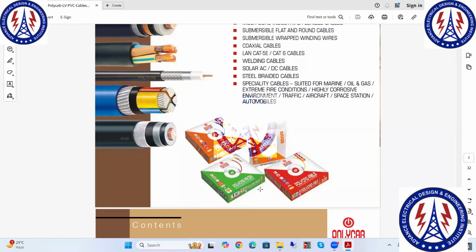No, FR is the fire retardant property. It is not related to the fault. Fault is sustainable; this conductor is designed based on the fault. Only for the smoke purpose we are using fire retardant.